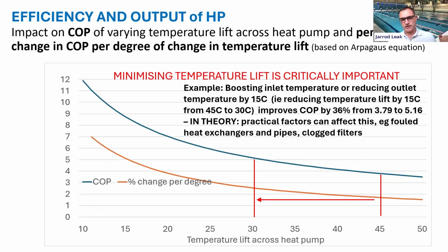This one I really want to emphasize as well. I've read a couple of feasibility studies and investigation reports for heat pumps, and this is often overlooked. You may be looking at electrical capacity, just generally what the boiler is you're trying to replace. But if you look at those plate heat exchangers, it's in that interface that is so very, very important. A few extra plates in those plate heat exchangers will save you a lot of money here. Right now your hot water loop is designed for 80 degrees going out and maybe 60 coming back. A heat pump needs to be below 60, ideally, and that smaller delta T means you need bigger heat exchangers, and the money is absolutely worth it there.